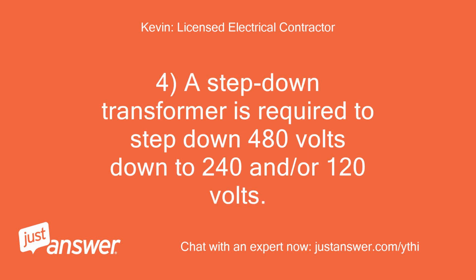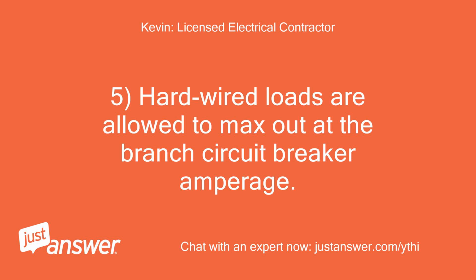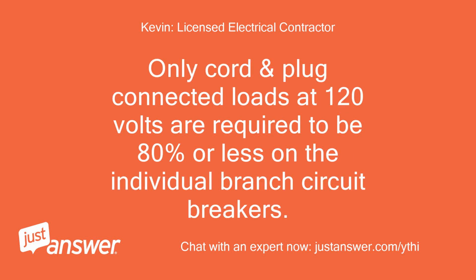4. A step-down transformer is required to step down 480 volts down to 240 and/or 120 volts. 5. Hardwired loads are allowed to max out at the branch circuit breaker amperage. Only cord and plug connected loads at 120 volts are required to be 80% or less on the individual branch circuit breakers.